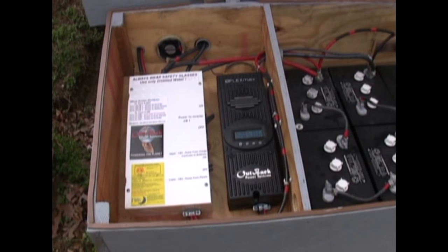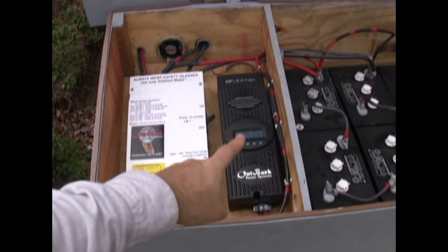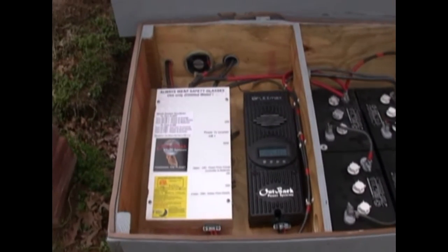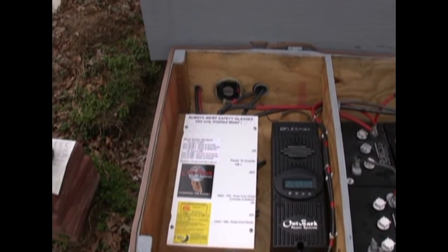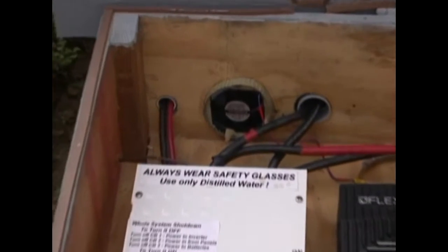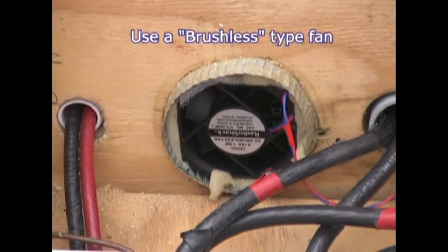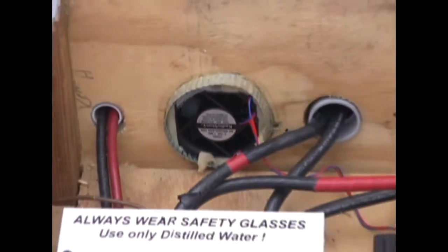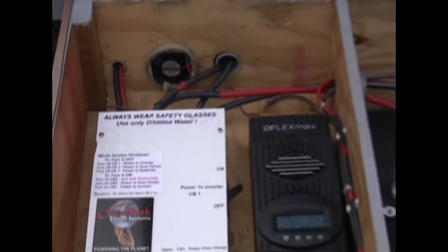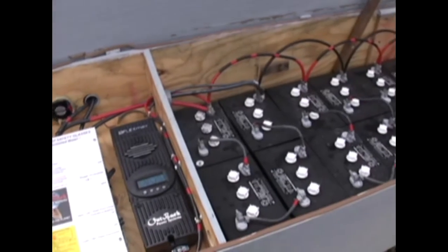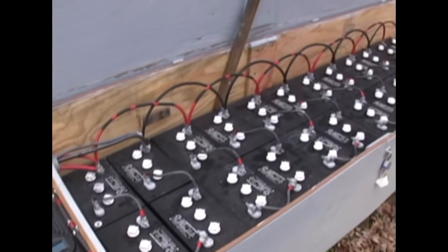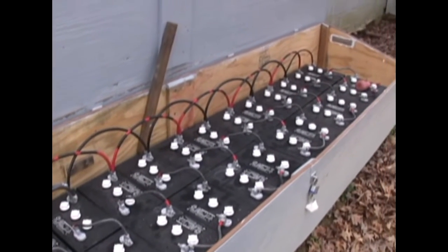Here's our main breaker box and our charge controller. Breaker box, charge controller, and our forced air blower. This is sucking air from underneath the house and blowing that temperature moderated air into the box and pressurizing first the electronics bay and then into the batteries. You see we have that separation panel there. That's optimum, especially in larger systems like this.